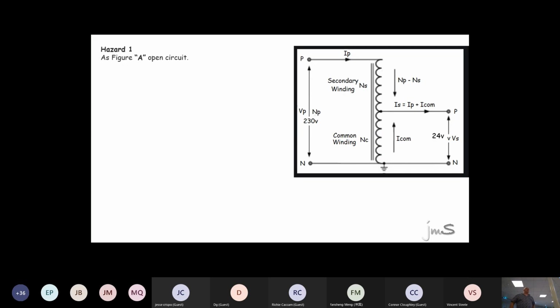So let's look at the first hazard, A. If you go and break that winding, see where A is flickering? Before I do that, I want to share: this is 230 volts, that's 24 volts. That current flows that way, and this one flows this way. Can you see those two currents cancel each other out somewhere?